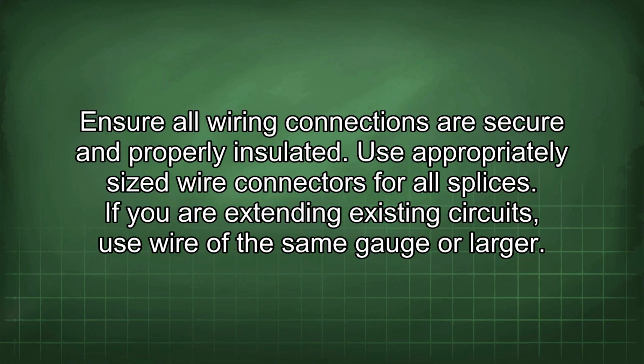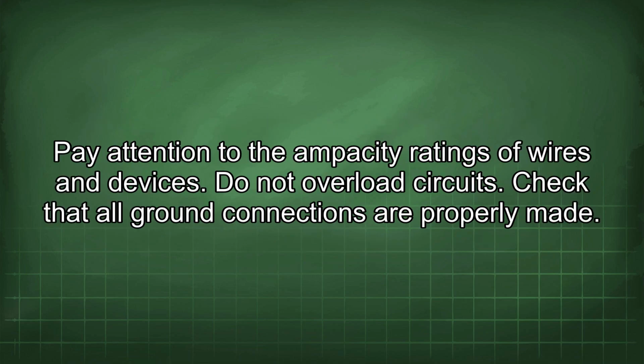Ensure all wiring connections are secure and properly insulated. Use appropriately sized wire connectors for all splices. If you are extending existing circuits, use wire of the same gauge or larger. Pay attention to the ampacity ratings of wires and devices. Do not overload circuits. Check that all ground connections are properly made.